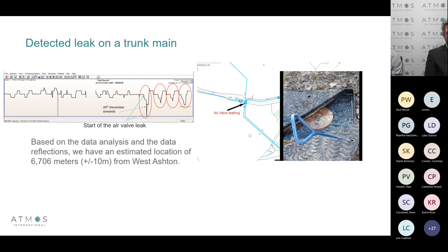And it just shows you, this is reconfirming why the negative pressure wave is such a useful technique, because one, it has a very fast response time, and two, it provides a very accurate leak location. And we're enhancing that further with that 60 hertz data, which allows us to see very subtle changes in pressure.